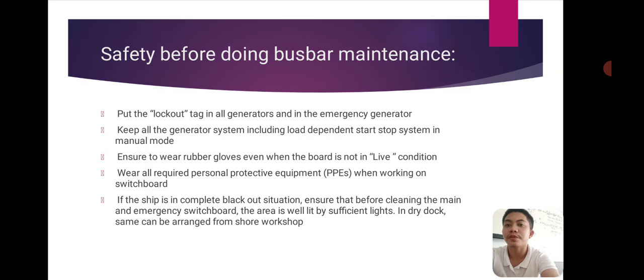Safety before doing bus bar maintenance. First, put the lockout tag on all generators and the emergency generator. Second, keep all generator systems, including the load dependent start-stop system, in manual mode. Ensure to wear rubber gloves even when the board is not in live condition. Wear all required personal protective equipment, or PPEs, when working on the switchboard. And last, if the ship is in a complete blackout situation, ensure that before cleaning the main and emergency switchboards, the area is well lit by sufficient lights. In dry docks, the same can be arranged from the shore workshop.